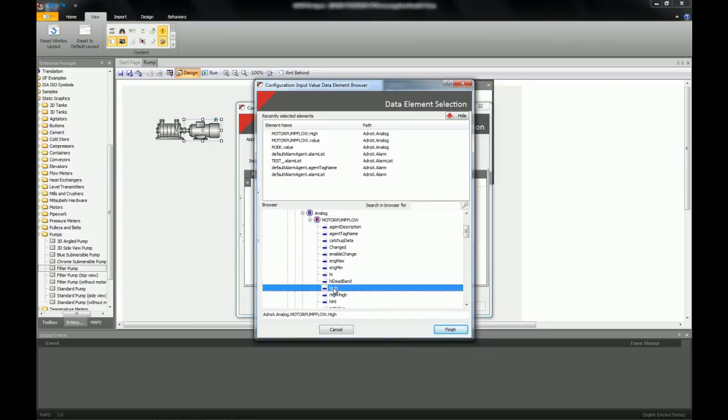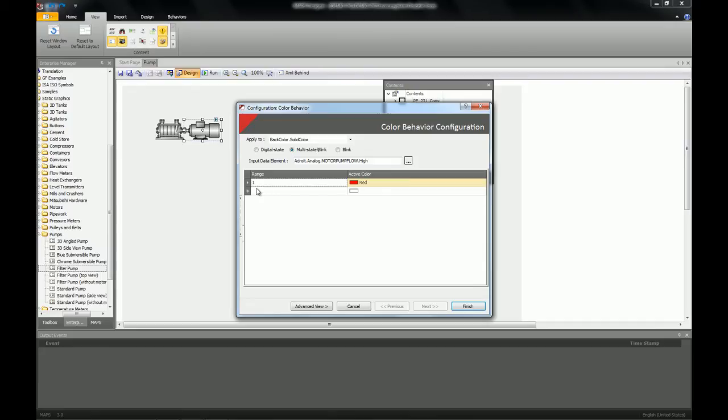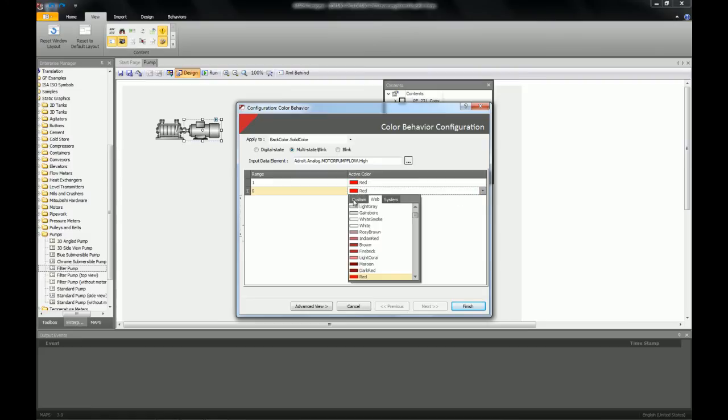This bit will go on when my pump, my analog value goes above the high set point. When it is above the high set point it will be 1 and my color will be red. When it is below that set point it will be 0 and my color will be green.